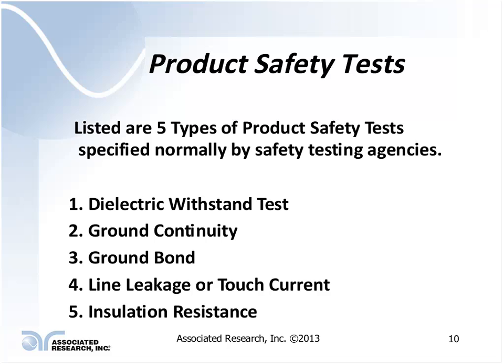Performing product safety tests. What are some of the common types of safety tests? The first one is the dielectric voltage withstand test, or Hipot. Hipot, where did that term come from? It's actually an acronym for high potential testing. Okay.